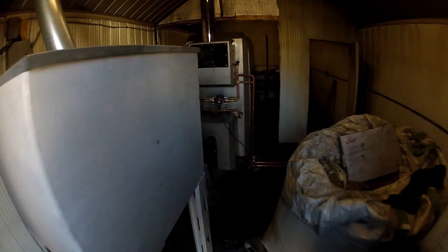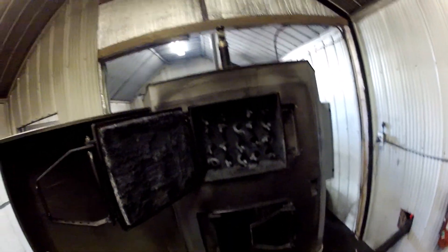I'll do a little bit of what some of the small maintenance stuff looks like today. The boiler is running right now at 166 degrees — it just started and it's got to go up to 170. There's the fire blowing away. I'll just do a little bit of maintenance here — turn the boiler off just for a few minutes and close this door or else it'll get smoky because the fan's off. Regular maintenance is just to open up this heat exchanger and give everything a quick clean. I'll start with vacuuming out the ash using this ash auger.